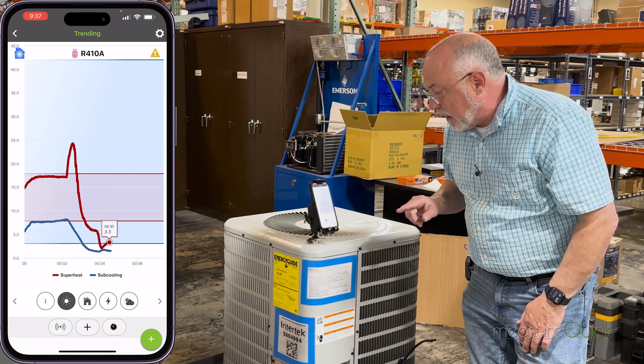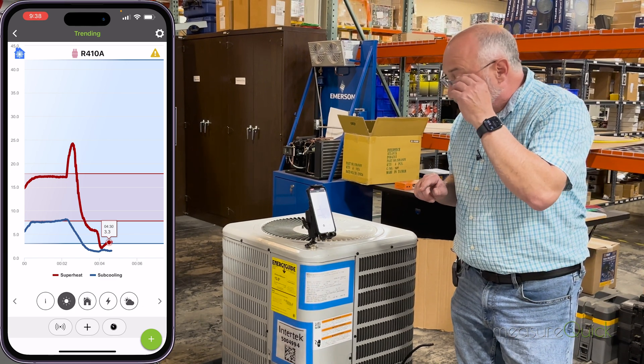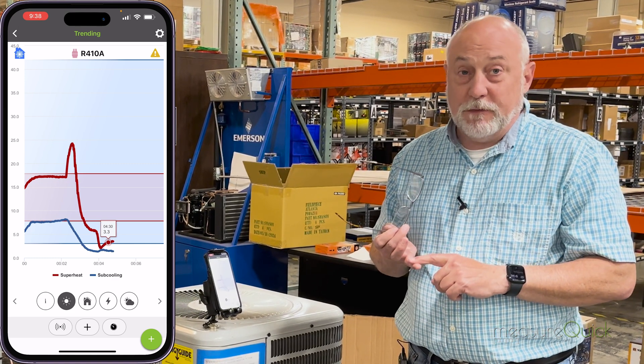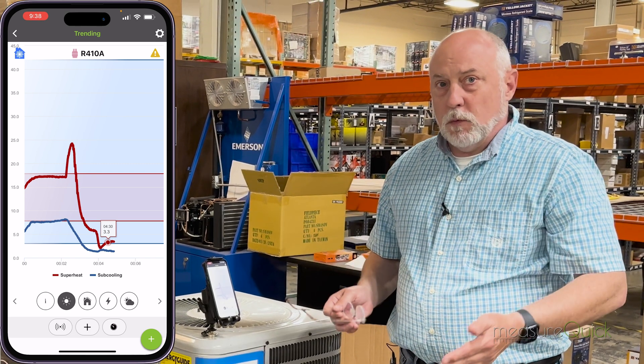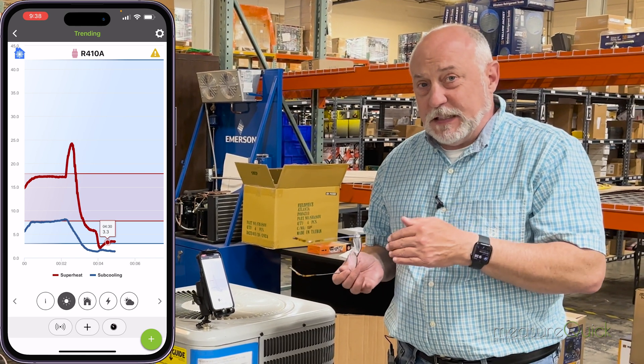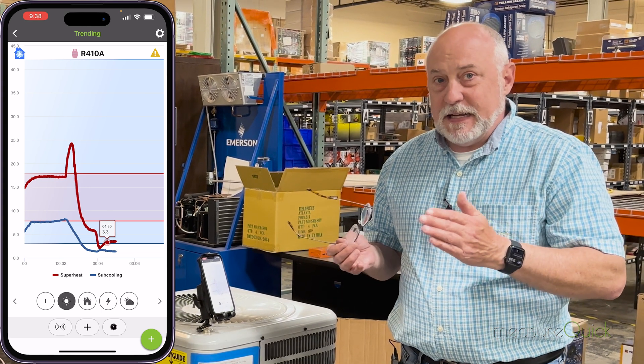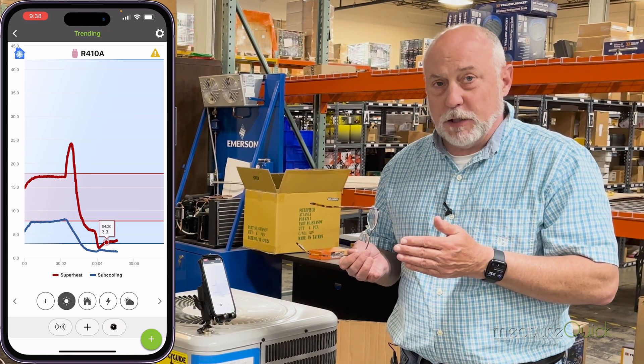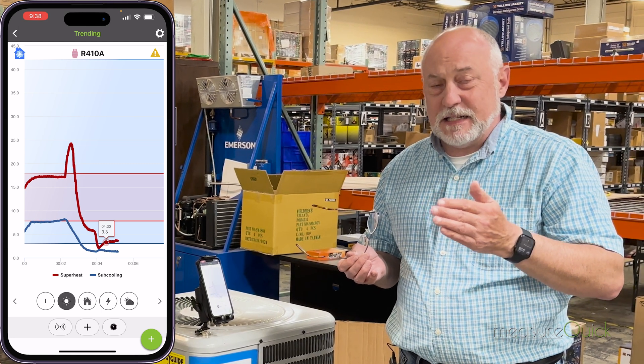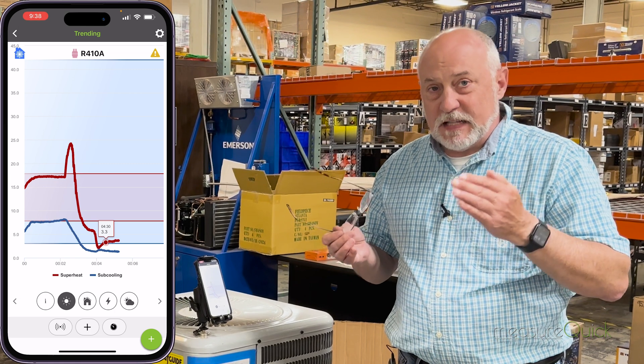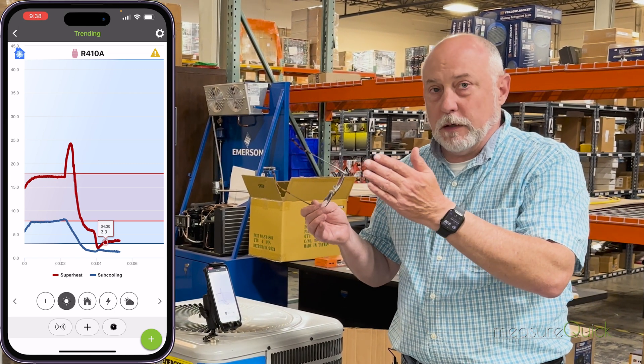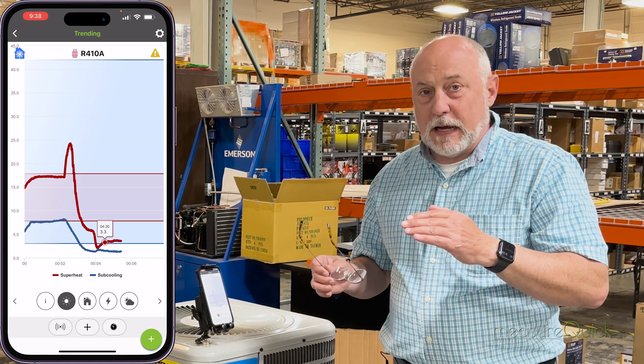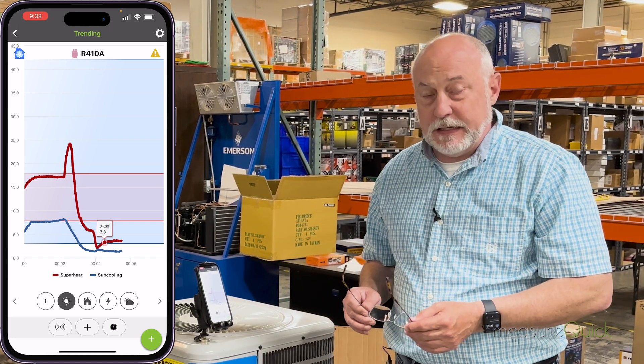We're at 3.3 degrees of superheat and coming up a little bit. This is an important concept to understand: just because we have low superheat does not mean that we're flooding. If that were to happen, every time we have a bad blower motor, we'd end up with a bad compressor, and that just doesn't happen. This is a fixed orifice metering device, which is like the worst-case scenario. A TXV's job is to control superheat, so the TXV would continue to close down and would probably maintain around 8 to 12 degrees of superheat. But even this fixed orifice system, even though we're effectively flooding the coil — meaning filling it up — is still maintaining a superheat of 3 to 5 degrees so we're not sending liquid refrigerant back into the condensing unit.